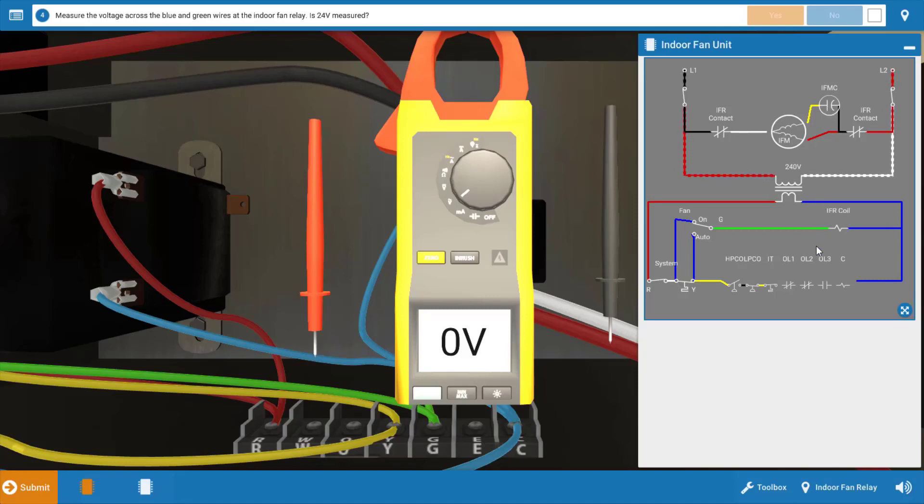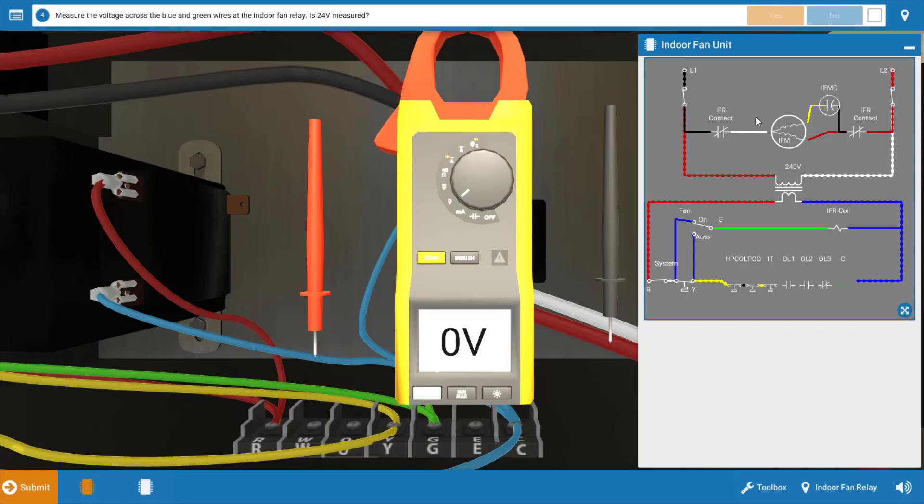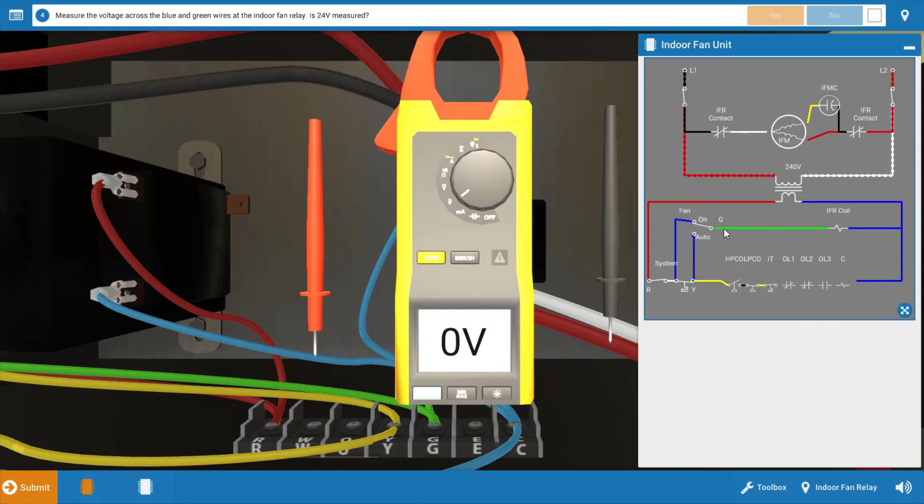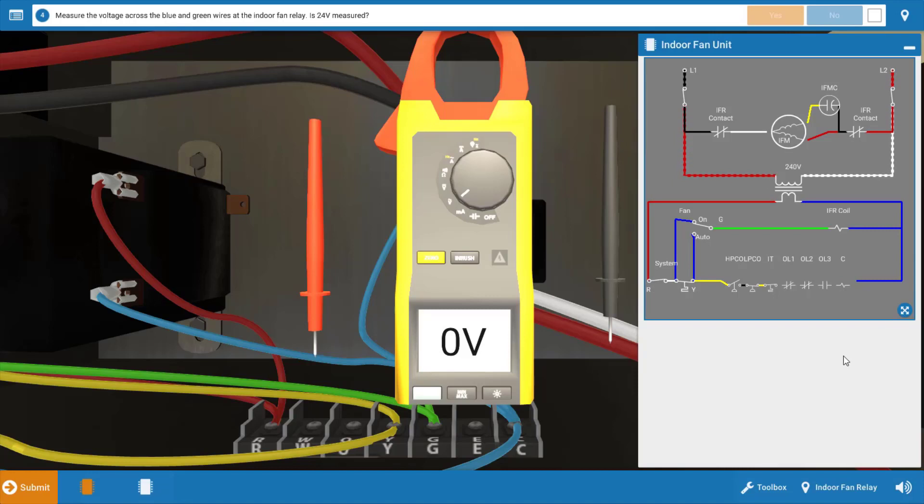But if you look in the low voltage circuit, there's a possibility that the indoor fan relay coil is bad here or faulty, meaning these contacts wouldn't close and the fan wouldn't come on. Serving the indoor fan relay coil is the fan switch within the thermostat, and this comes out of the G terminal. In other words, 24 volts comes out of G and sends it to the indoor fan relay coil. And when that energizes, it'll close its contacts and turn the indoor fan motor on.